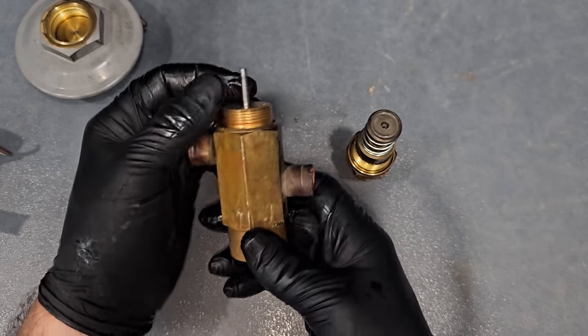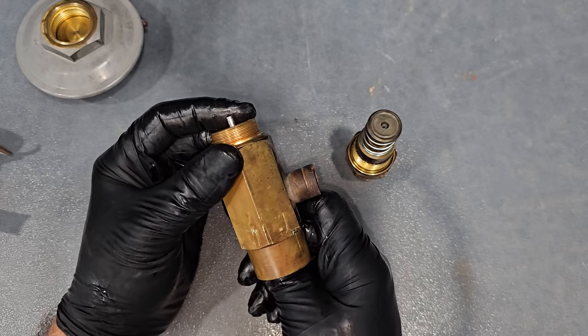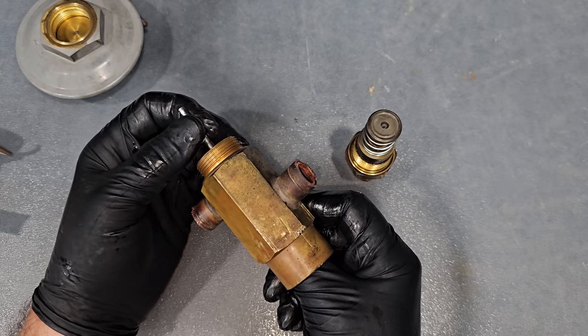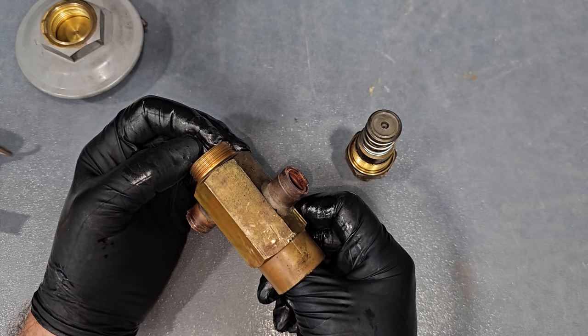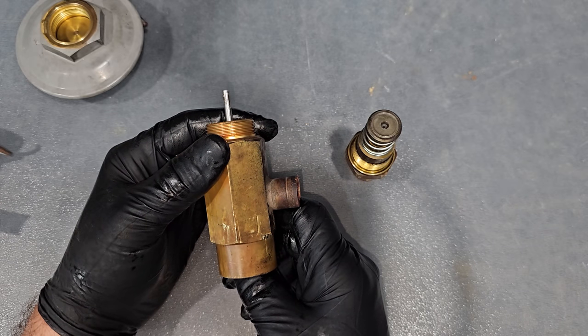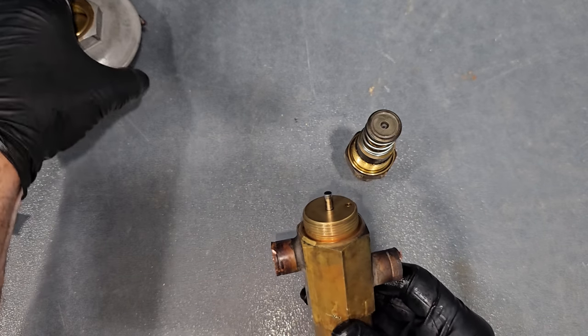So I think that this valve failed due to the high system pressures, because that condenser always gets plugged up. The customer doesn't do enough routine maintenance. They do routine maintenance, but not enough. And we're constantly having to clean that condenser because of the placement of the rack next to the exhaust fans. And that's what caused our problem with this guy, okay?